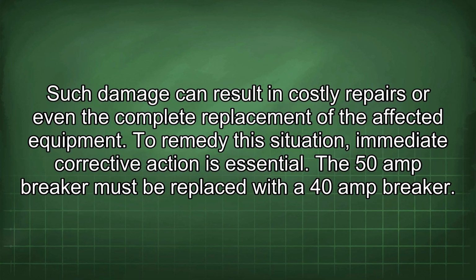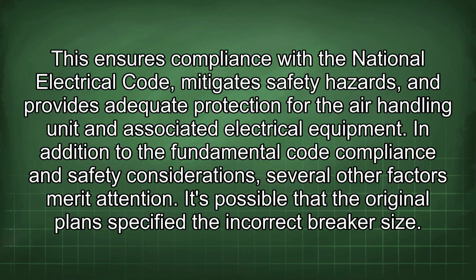To remedy this situation, immediate corrective action is essential. The 50 amp breaker must be replaced with a 40 amp breaker. This ensures compliance with the National Electrical Code, mitigates safety hazards, and provides adequate protection for the air handling unit and associated electrical equipment. In addition to the fundamental code compliance and safety considerations, several other factors merit attention.